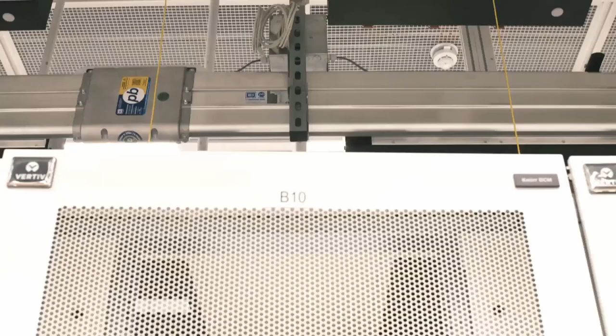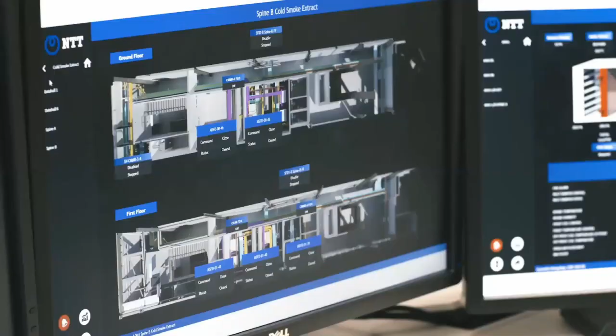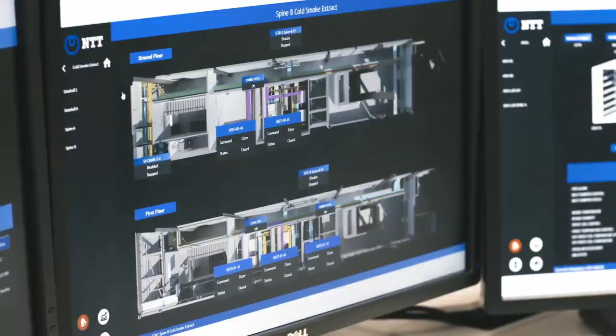You'll see from the views inside the hall, we use a fan wall design for the cooling, with heat rejection into the ceiling via a hot aisle containment system. This allows us to improve our mechanical efficiency. Within the data halls, we have 32 megawatts of capacity at a density of 2.5 kilowatts per square meter, meaning we're able to accommodate hyperscale compute and high density computing from our customers' requirements.